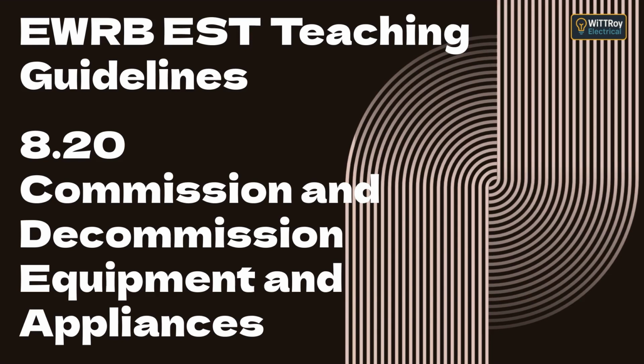Switches and fuses are in the active conductor only. 2. The neutral is never switched or fused, except in specific cases, and 3. The earth remains continuous throughout the system. If polarity is reversed, a switch might interrupt the neutral instead of the active, leaving the appliance body still live even when turned off. That's why every reconnection must include a polarity test using a meter or polarity indicator. In short, correct polarity means only the active is switched, and the metal parts stay safe to touch.